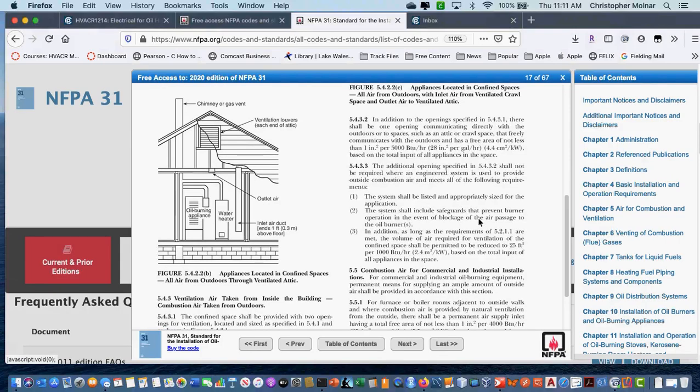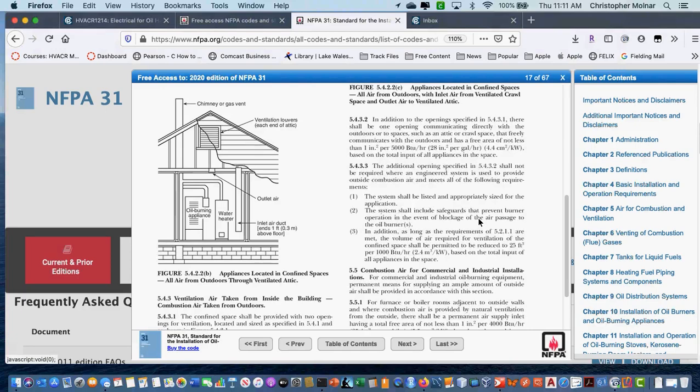Well, once you put in the new boiler based on the new code, it doesn't mean that you have to constantly switch it every time the code changes, right? That's correct. It's basically any time you pull a permit for an equipment installation or replacement. Now, if I go out and service something and see that there's an unsafe condition that's resolved in the new code, I can't tell the homeowner you have to fix it. But I might explain it to the homeowner and say, you know, it might be a good idea to fix this.